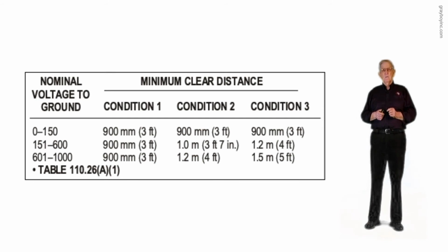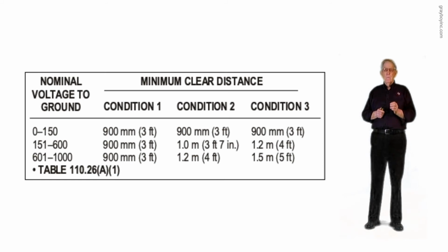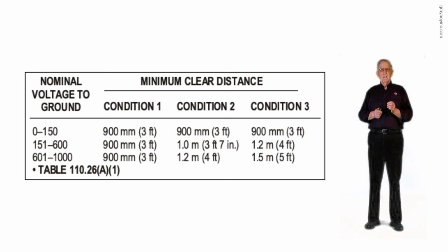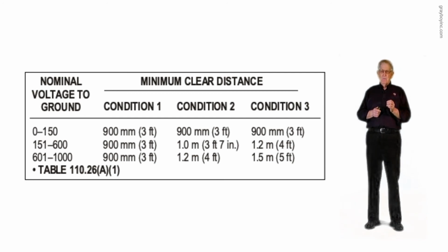Now, this same rule is going to apply to outdoor equipment. But notice the note 1, which is new in the 2020 NEC. Outdoor structure overhangs or roof extensions shall be permitted in this zone as outlined and permitted in 110.26(E)(2) exception.